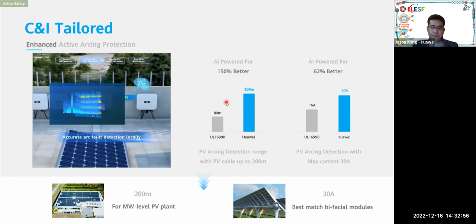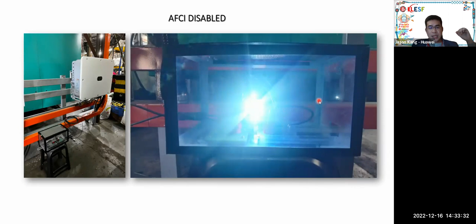So this is another illustration that we did at an actual site. This is when AFCI is disabled. Yeah, we can actually enable and also disable the function. So when AFCI is disabled, as you can see here, we try to create a gap of an actual arc fault. This is live at an actual site. Yeah, so we create an arc fault. So as you can see, this is a bluish color, and the temperature is over 3000 degrees Celsius, right? And this is what we want to avoid, lah. So I will take a look at another scenario, when AFCI is enabled.